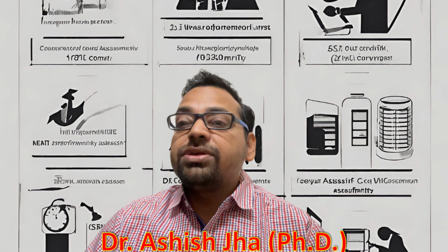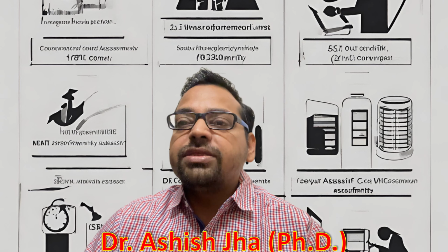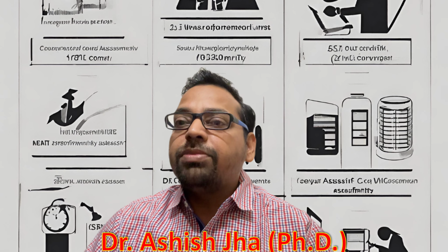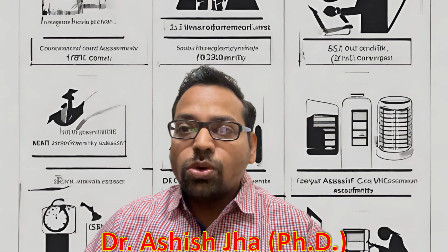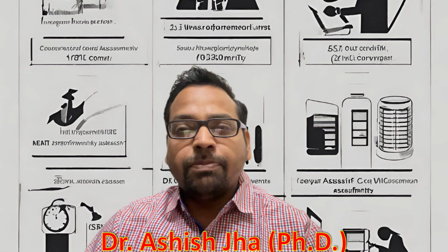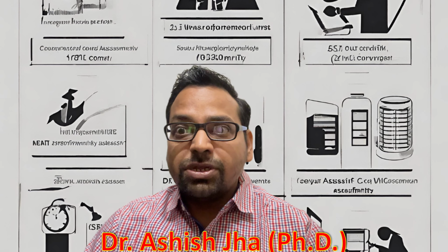And that assessment of each and everything, whether it is clinical data, in vitro data, or in vivo data, whatever information they have related to the manufactured medical device, they assess each and everything, and that assessment is called the conformity assessment. And once the manufacturer feels that everything is on the correct way, the procedures and protocols are followed in a very regulated and proper way, only then do they decide to send all these documents and data to the regulatory and authorizing body before getting the medical device into the market.